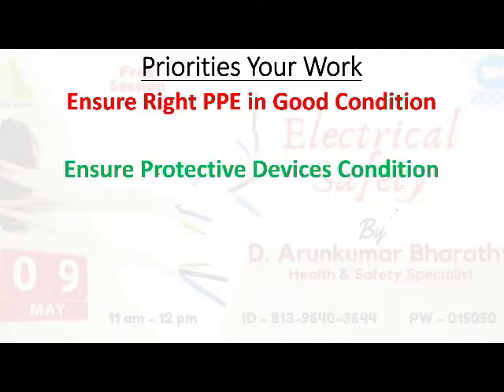We have to ensure the protective device condition - I'm talking about trippers, circuit breakers, and sensors. Check the ELCBs and surge arresters and all protective devices you're using to confirm their condition. And for protective devices to perform properly - for example, if a circuit breaker has to trip within 25 milliseconds - proper earthing is very mandatory.